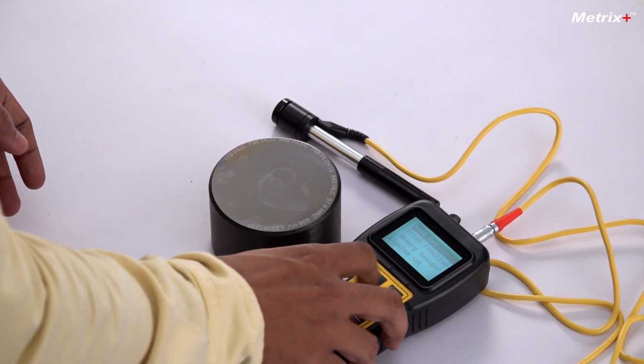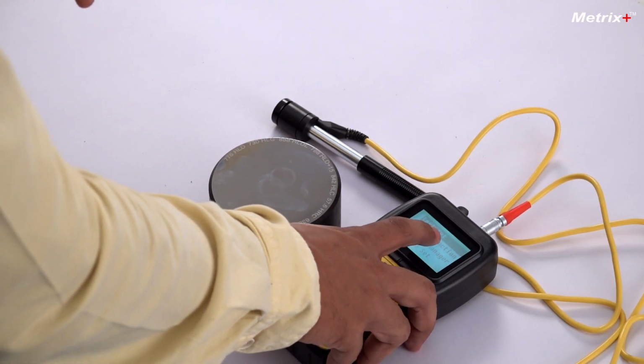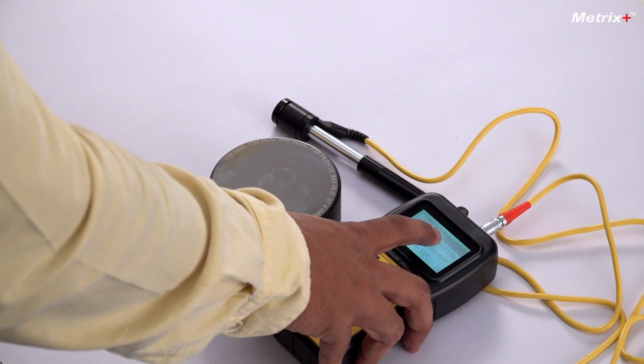So this is the menu button. First thing is, this instrument can also show you the average value. Like you have a surface and you measure on 3 different points to get the average. That is how usually hardness is measured, because different points might have different hardness, but the average value is the hardness of the entire material. This test set is where you can change the average value times.